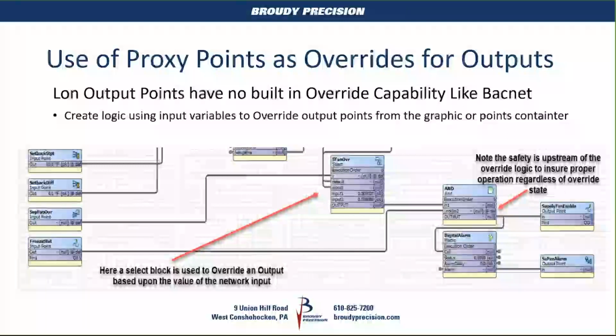So the point of this slide is that I use an input variable connected up to a select block, and the select block creates the logic for my supply fan here. The other point I was trying to make is that when I create overrides, I also keep them downstream of any safety logic that I might have.